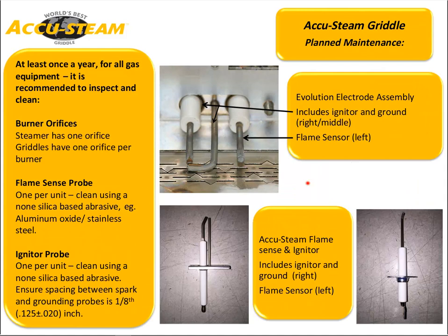The final thing I want to discuss today is planned maintenance, also to give you a good visual of what our flame sensors and igniters look like. So the one above here is for the steamer. We have our flame sense rod, grounding rod for the igniter, and the igniter probe itself. Below, we have the flame sensor for the griddle, and then, again, grounding rod and igniter probe for the griddle.